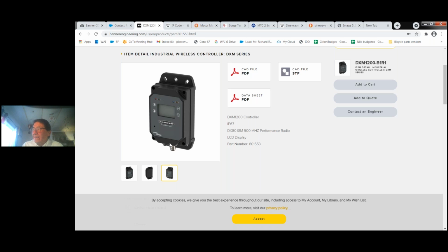So this is the first thing you put on: you stick it on the side of the can. It's IP67. You wire it to the VFD's Modbus port, and allow the cell communication to connect to a server on the internet. The next piece in the link is your smartphone, tablet, laptop, or computer that connects to that same server with an address.